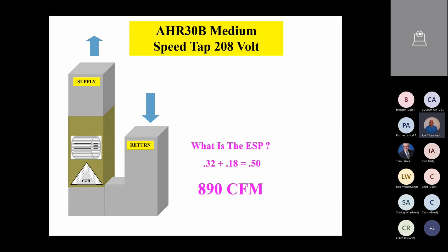Any questions or comments? Yes, good morning. I got one question. Come on. So the illustration that you have here, blower on top, coil on the bottom, that basically describes most of our air handlers around here. Yes, sir. And in this illustration, our probe placement was in the return duct drop and the supply plenum. Correct. Earlier, I believe, unless I misunderstood, if it were an open return, we would be taking our return probe and putting it after the evaporator coil into the cabinet of the unit. Is that what you would recommend?